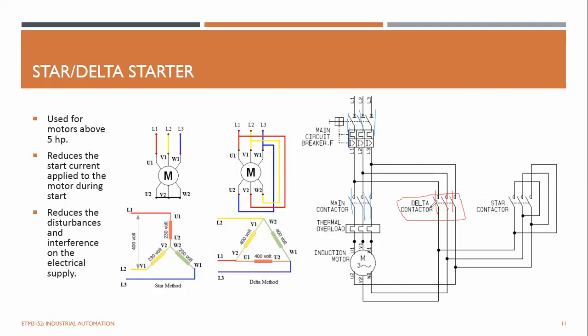So once it reaches full load, this delta contactor is closed, which means L1 comes here and goes to V2, right? L1 comes and goes to V2, and the other one down, L2 comes here and goes to W2. L2 goes to W2, and the other one is L3. It goes to U2. L3 goes to U2, right? Likewise, it's making a delta connection. So the circuit is completed now.